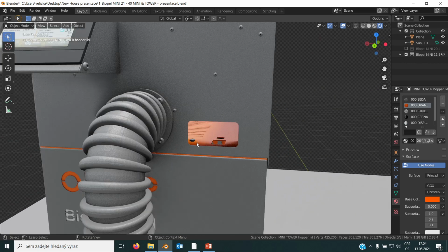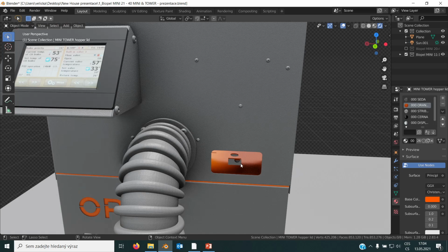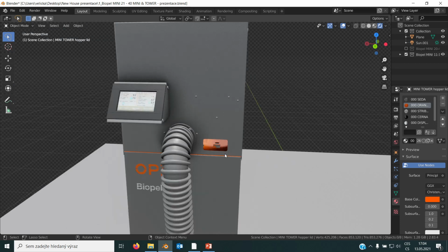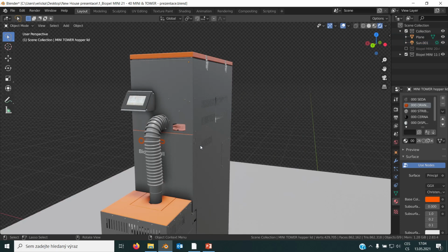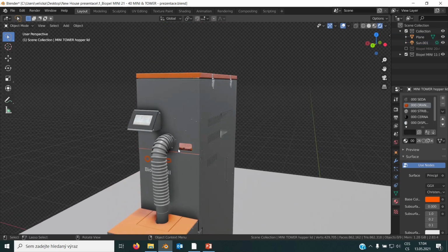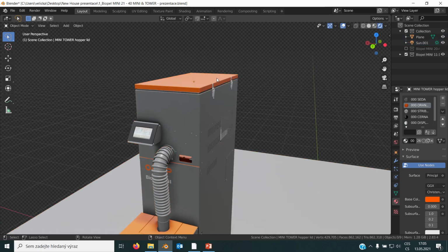In the front there is again a hole for the main power button. There is a main power switch here, so to have access to switch the boiler on and off, you have a place here to be able to reach the main button. And the last thing about the tower version of the pellet hopper is that when the boiler is in operation, the main lid on the top of the hopper needs to be always connected, and always placed on the top of the hopper.